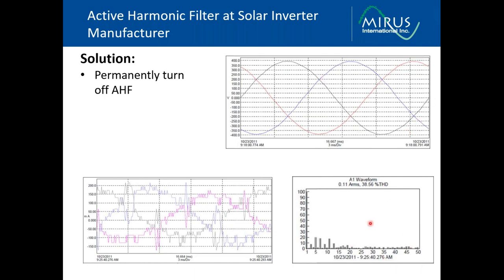The spectrum on the current, the high frequency harmonics introduced by the IGBTs were gone. This is the current now being drawn, much lower levels of current. And the manufacturer of the active harmonic filter tried to adjust their input filter, their input passive filter. It didn't have any significant effect. Ultimately, the only solution was to permanently turn off the active harmonic filter.